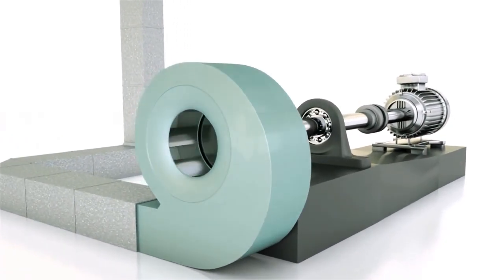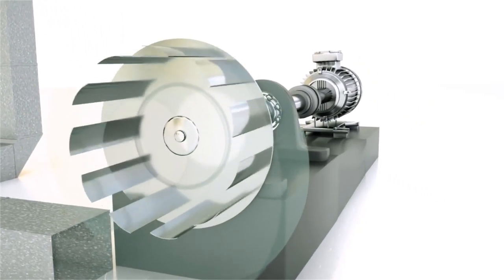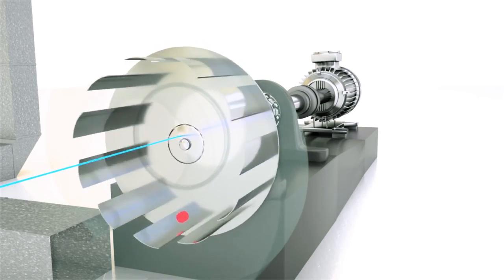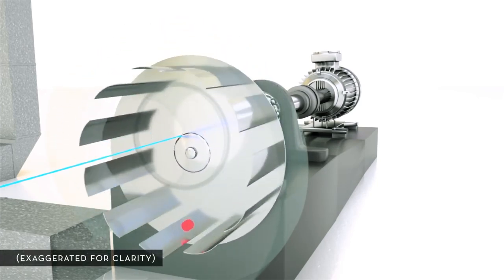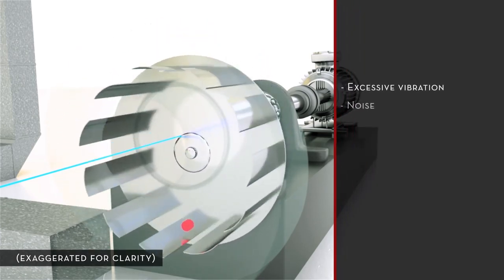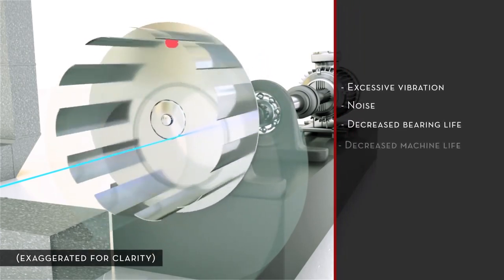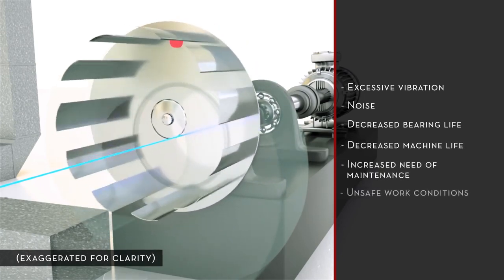Rotational unbalance occurs when there is an uneven distribution of mass around an axis of rotation. It can give a rotating machine element eccentric movement, which can cause excessive vibration, noise, decreased bearing life, decreased machine life, increased need of maintenance, and unsafe work conditions.